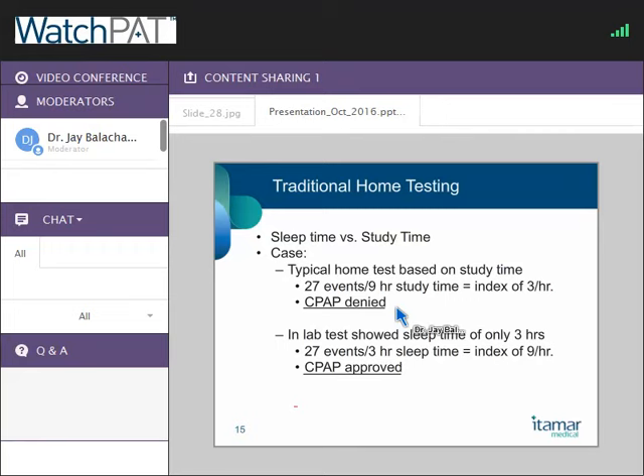As it currently stands, the current WatchPAT device is able to pick these events up — it simply will not be able to distinguish them as central versus obstructive. However, on the horizon is a modification to the WatchPAT device that's going to add that level of granularity. The difference is all in the chest body sensor and snore mic — with a change in how that body sensor works, we now have the ability to detect efforts specifically and report central and obstructive events. So this will be coming.